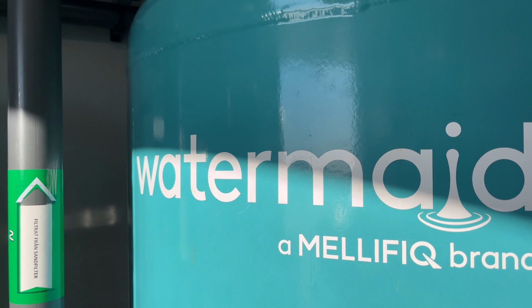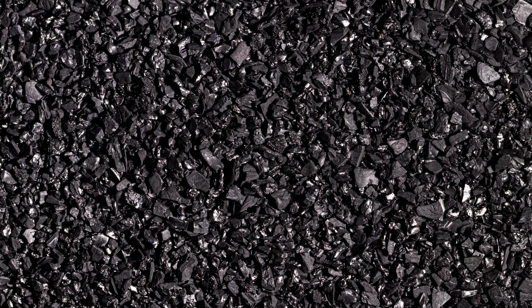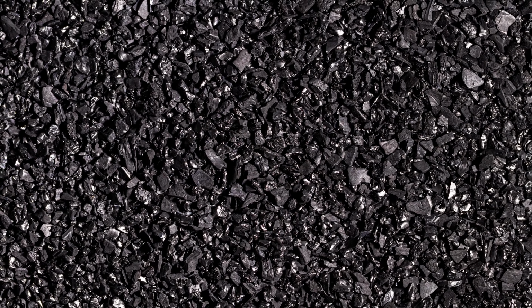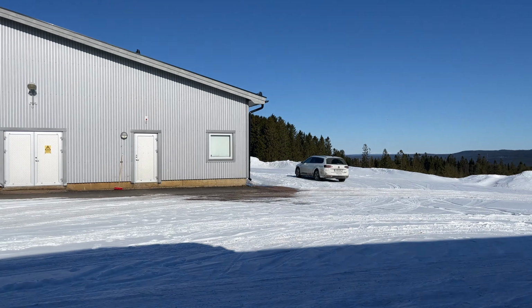The treatment process undergoes a final polishing step before safe release into the recipient using specifically selected catalytic and impregnated media to remove any residual oxidation transformation products or APIs from the upstream treatment steps. The combination of pre-treatment, advanced oxidation, and adsorption generates ample redundancy to ensure micropollutant removal rates far exceeding current and future requirements without the use of any chemicals.